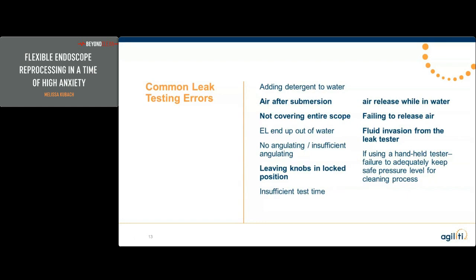I also see a lot of endoscopes that aren't entirely covered throughout the cleaning process, often due to leaky drains, sinks that are too large, or fill time that's too slow. When you don't fully cover the scope, it can leak from anywhere and you may miss a leak. Also, during your leak test, make sure the knobs and the variable stiffness adjuster knobs are in the correct position.